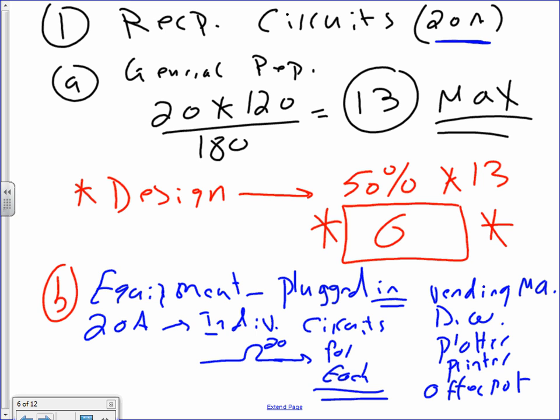Now design. Remember, we're engineers. When we design in a commercial building, this factor that you see here is called CSK. Anybody know what CSK is? This is my initials. So if somebody asks you where the heck that number came from, tell them Chad. Design factor. Remember, these are commercial buildings. These circuits can be overloaded in a commercial building. Some of them are used for general use in offices and so forth. So you throw a 50 percent derating factor. If you take 50 percent of 13, what do you get? 6 receptacles. That's where the number 6 came from.